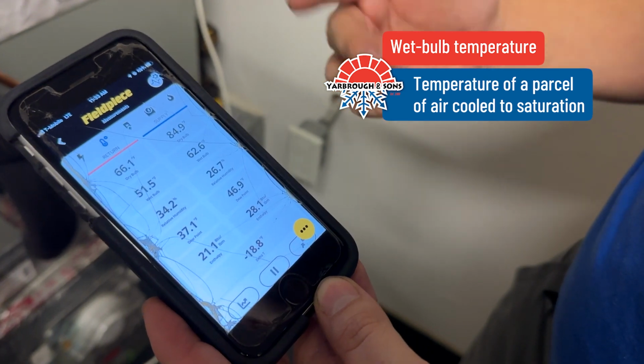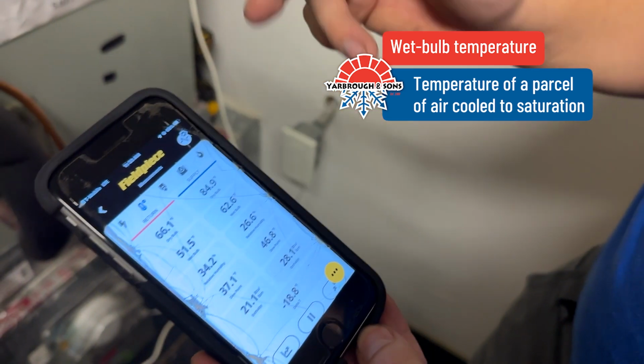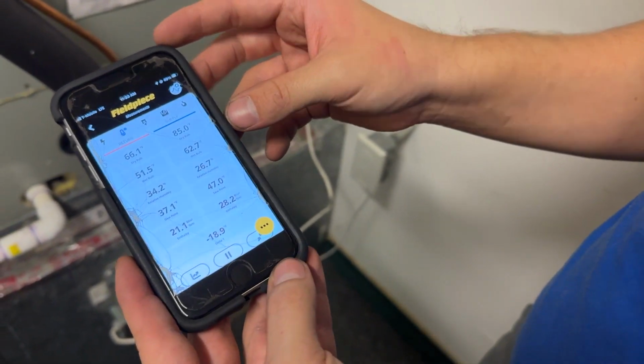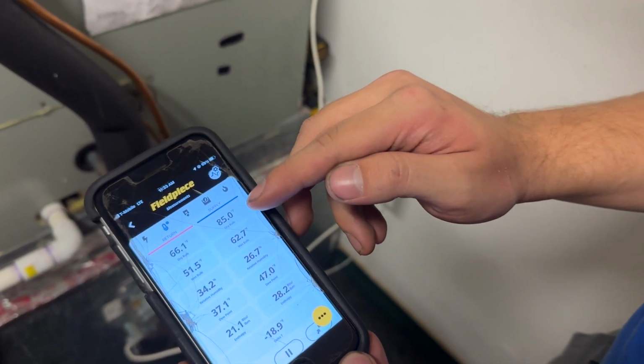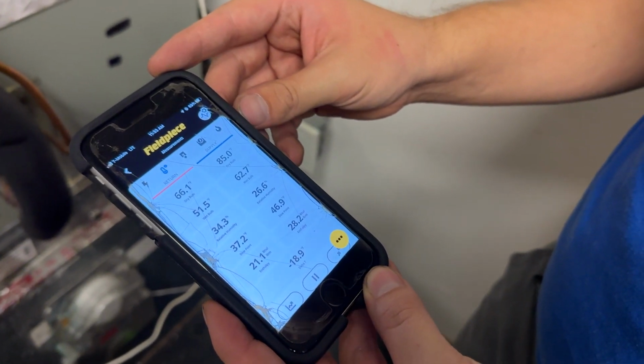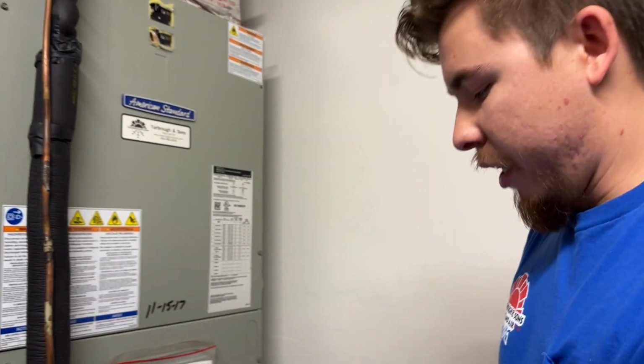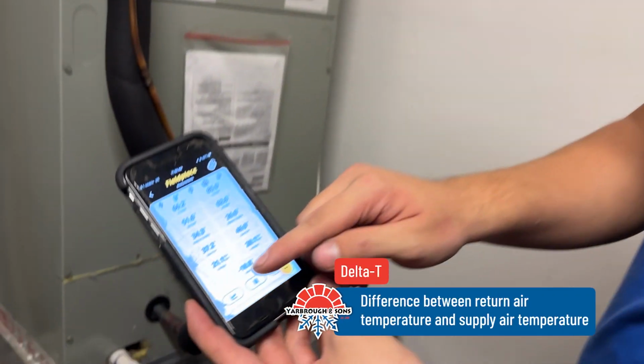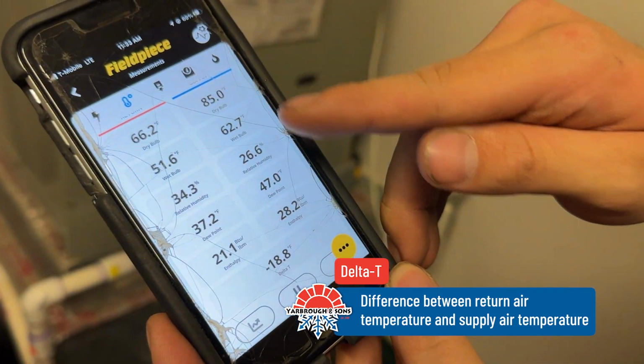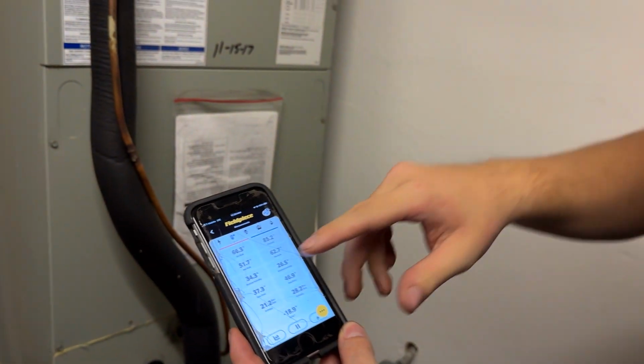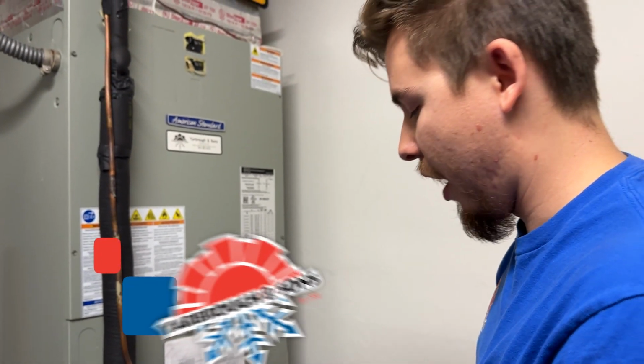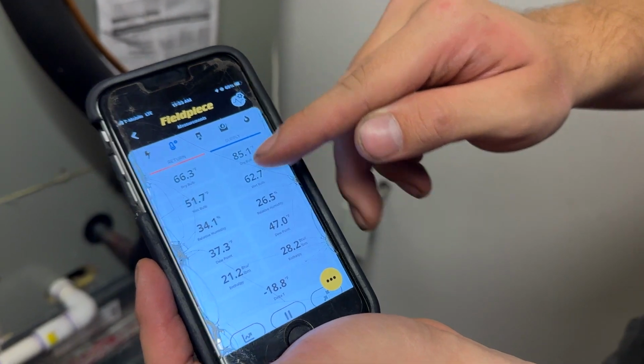Then it lets us know here's our wet bulb, our humidity, our dew point. And you usually want that range to be about 20 to 35 during winter time. So we've got 66 degree air coming in, about 85 coming out. Like I said, we just now put them in, so it's going to take a little bit to run properly. Your delta T right here is at the bottom. All it is is the difference between your supply and return. So it's the hot air pushing out, and the return dry bulb is the air sucking in. Usually in winter time you want about a 20 to 35 degree difference, and that's what the delta T is on the probe here. It's just the difference between the supply and return dry bulb.